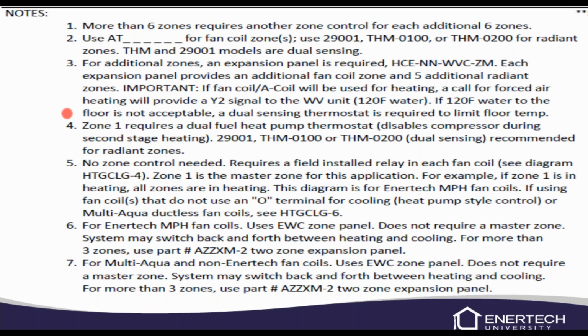The EWC zone panel is made for air dampers, so what happens when there's no call to any zone is all the dampers are wide open. Well, we don't want our water valves to be wide open when there's no call. So we use one of the zones on the EWC as a dummy zone, and we'll jumper R to G, so that zone always has a fan call. And that way it'll power those water valves closed when they're not in use.